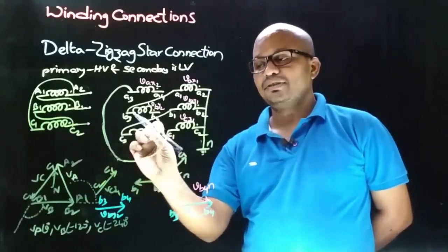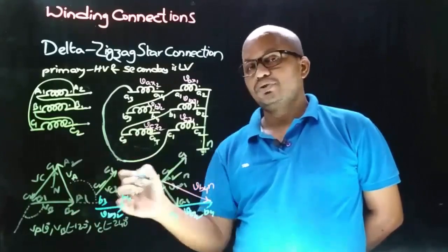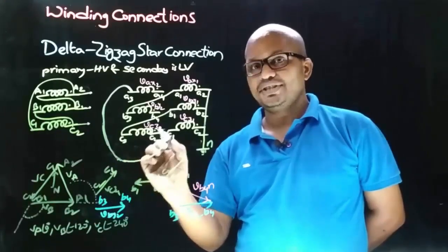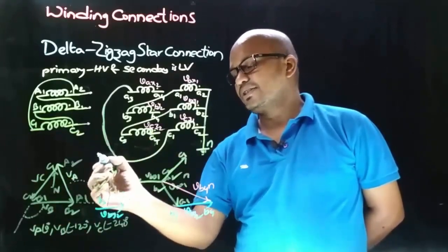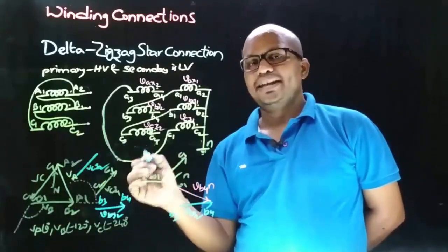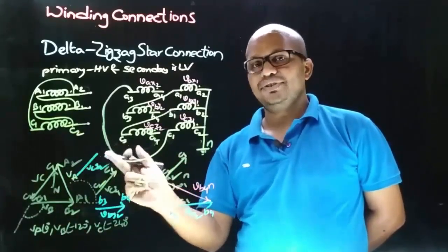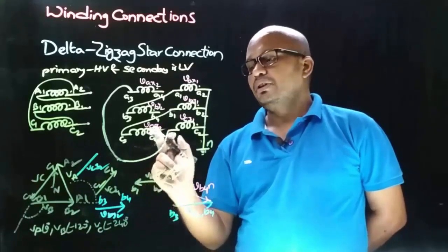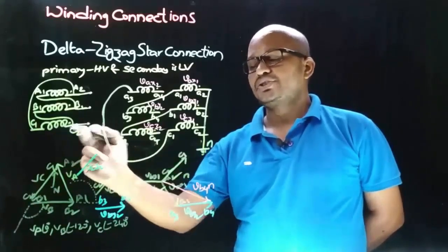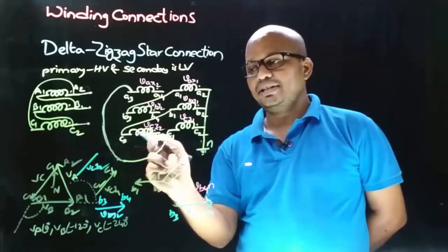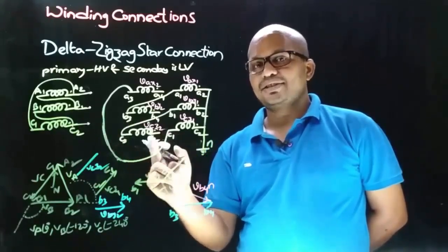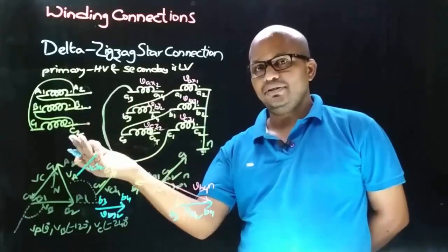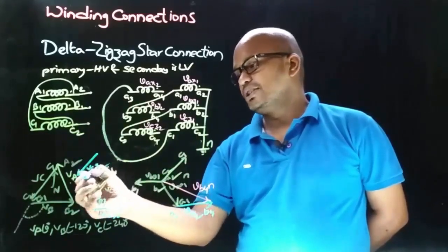Now coming to this B1 connection, B1 is having C3, means to B1 there must be a C3 connection. Therefore now we must draw the VCZ2 phasor. So drawing the secondary side VCZ2 phasor parallel to the primary side VC phasor somewhere here like this. And now we need to decide the direction of this VCZ2 phasor. Observe that on the primary side the connection is taken from the dot end, and on the secondary side the connection is taken from the dot end. Therefore, the secondary side phasor direction will be the same as that of the primary side phasor. So the direction is like this.